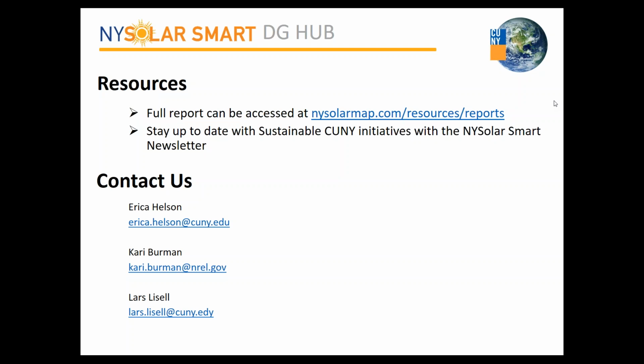Could I throw one more thing in? I think documentation is key to proving the system is integral and that it's charging 75% of the time from renewable energy. When the system is designed and submitted for interconnection, make sure the engineer documents that the battery system is integral to the solar array for specific reasons, or that it's charging 75% of the time from renewables because the control is set that way—ensuring it's only charged from solar, not the grid.